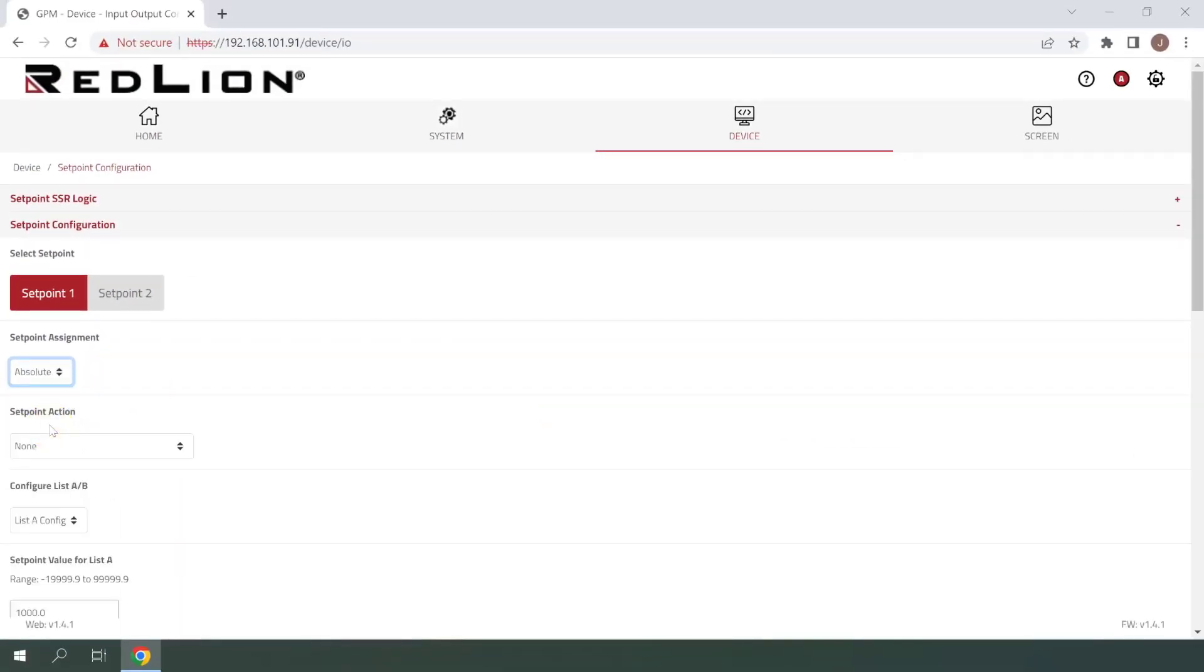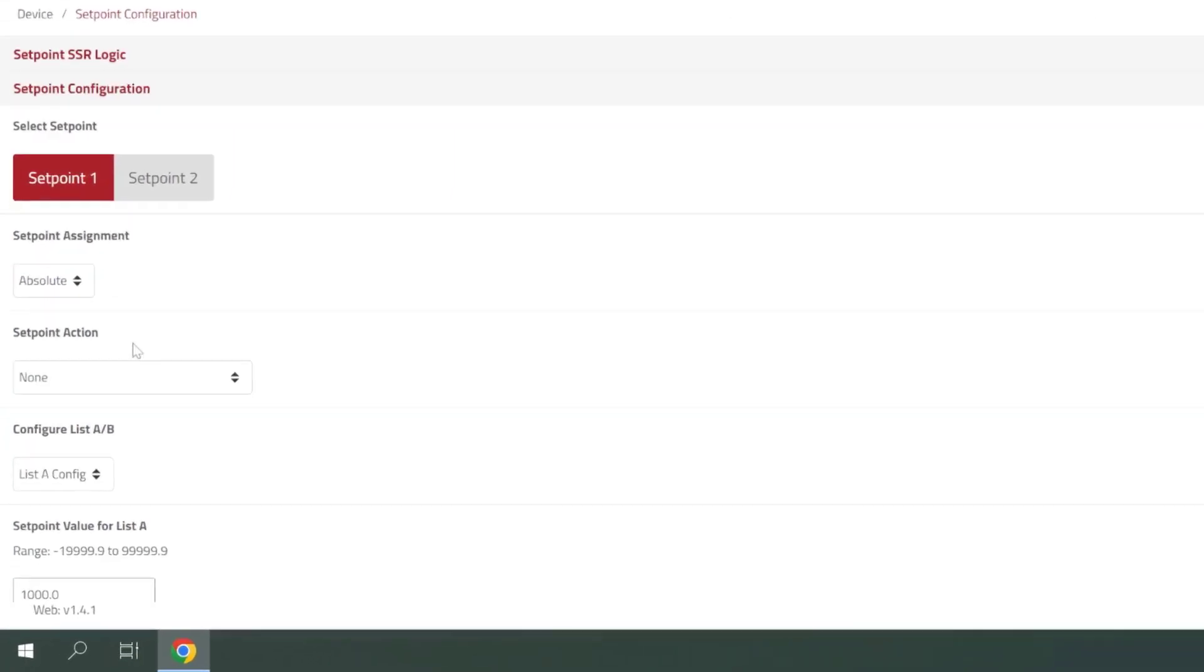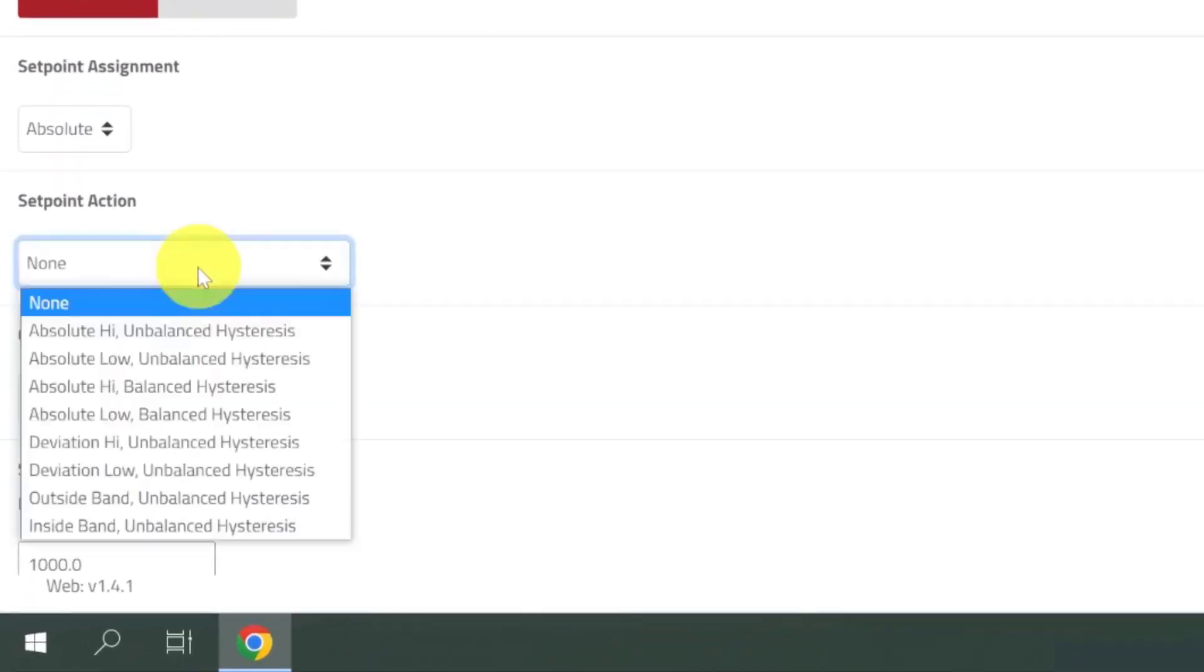Once that selection has been made, you'll see a number of new settings available, starting with Setpoint Action. Here, we can use the drop-down menu to select how we would like the setpoint value to be compared to the measured input value, in order to be triggered. Options include Absolute High or Low, Deviation High or Low, and Outside or Inside Band.